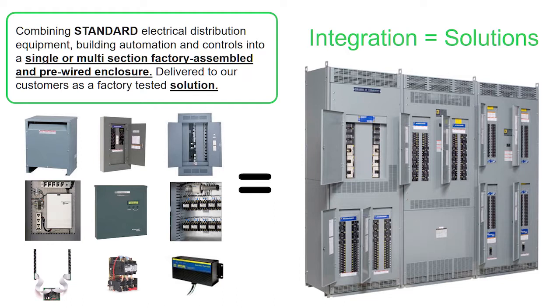Looking at the photograph on the right, starting in the upper left-hand corner, that is an I-Line panel board, which is 480Y/277 three-phase four-wire for protection of large motors, etc. Directly below that, as well as at the top of the middle section, are two NF panel boards, which again would be 480Y/277 — most likely for 277-volt lighting and smaller 480-volt loads than what would be found in the I-Line panel.